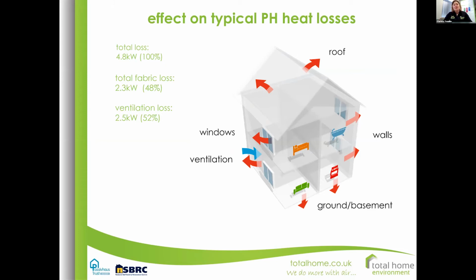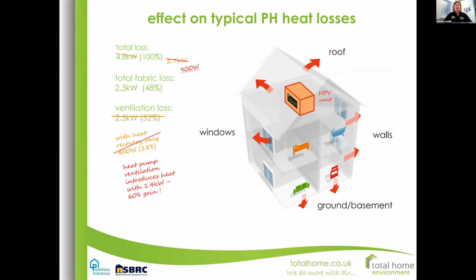So with regards to heat losses, typically in probably a passive house type house, your total heat loss could be about 4.8 kilowatts, with almost half or more than half in this case associated with the ventilation side of it rather than fabric side of it. So it is quite a serious loss that we're talking about just to get fresh air into your home. So if you put a heat recovery ventilation unit into the mix, you're severely reducing that heat loss. And if you put heat pump ventilation, instead of a loss, you're actually getting a 60% gain. So you can see how effective this technology is in helping create a lovely home environment.